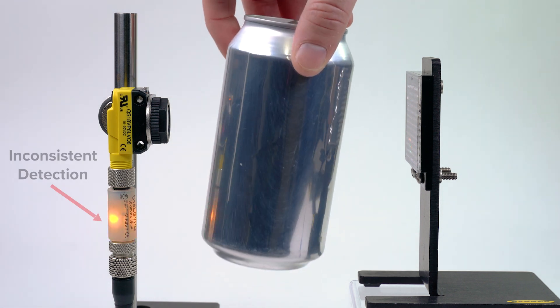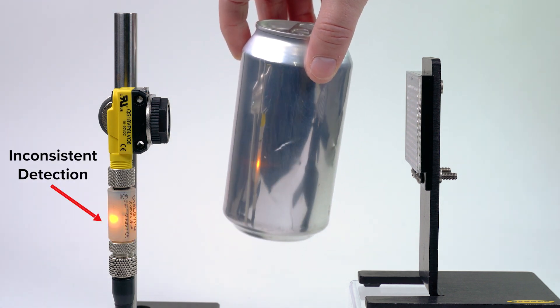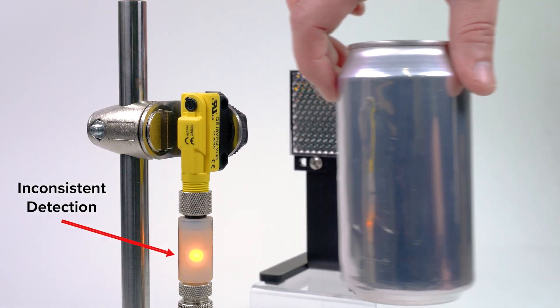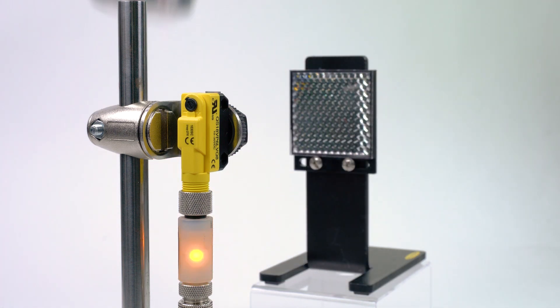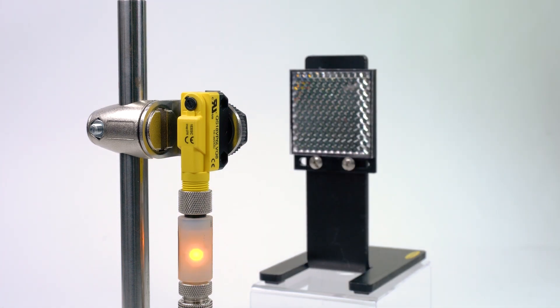If the target object has a highly reflective surface such as shiny metal, shrink wrapped packages, or reflective poly bags, a traditional retro reflective sensor may be unable to tell the difference between the object and the opposing reflector.